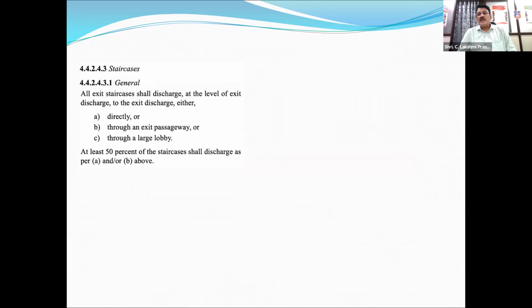Then if we are providing staircases in a high-rise building especially, or a normal building also, at least 50%, if you are providing 4 staircases, at least 2 staircases, should be either on the periphery of the outer wall of the building, or they should be through a protected 2-hour rated corridor. You cannot leave the people just like that on the ground floor to go normally. That should not be the case. They should be moving through a protected corridor, or they should directly exit to the outside of the building. At least 50% of the staircases have to be like this, directly or through an exit passageway or through a large lobby. At least 50% of the staircases shall discharge as per A and B above.